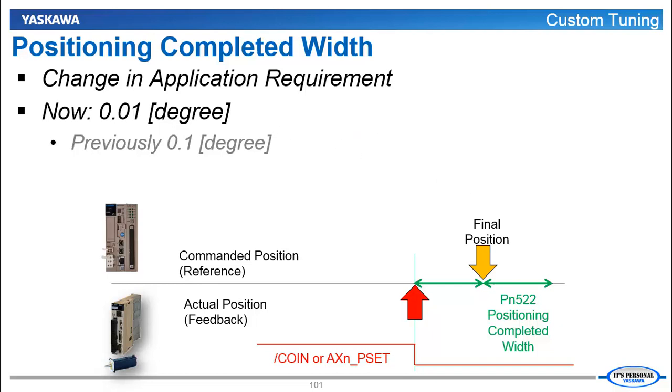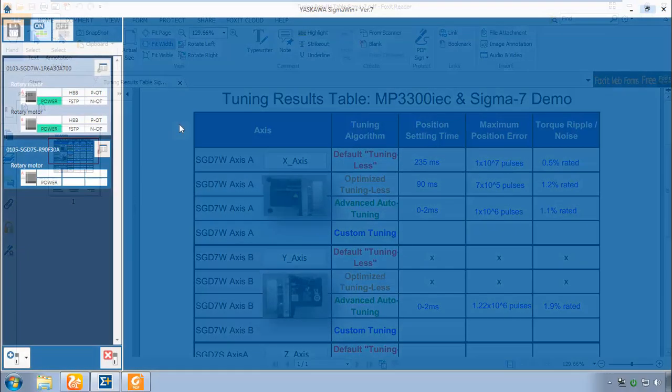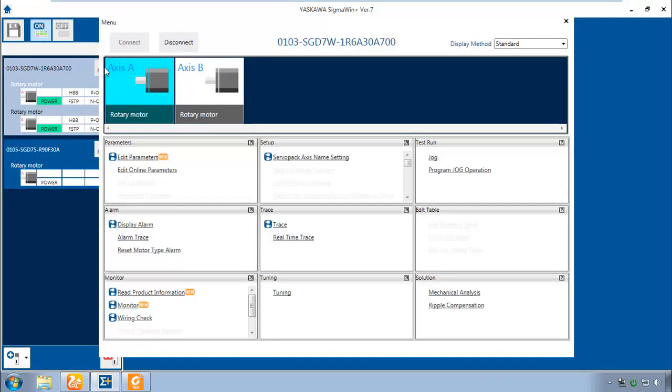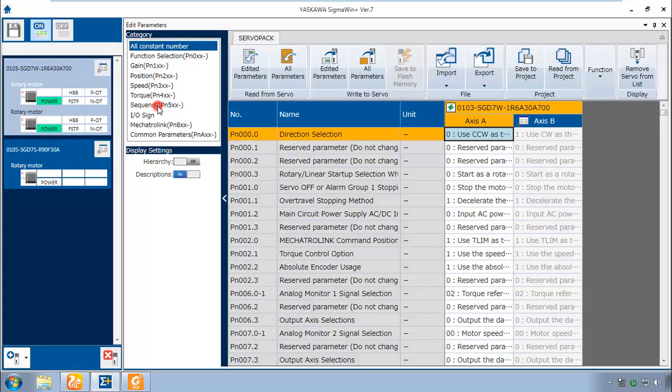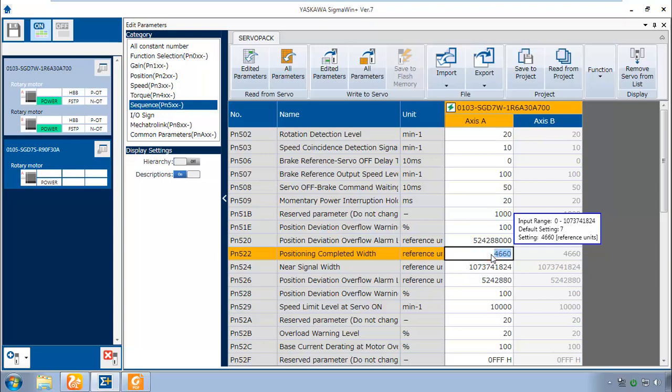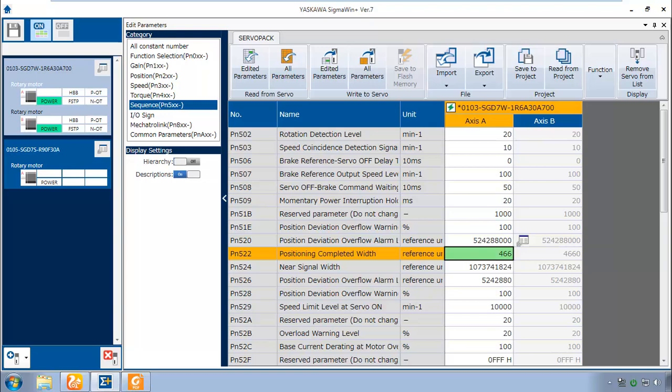So now to measure the coin signal, what parameter has to change? It's PN522, Positioning Completed Width. And what do we change it to? What value will give us 0.01 degree? Let's open up the parameters, go to the PN500s. And you remember we've set PN522 to 4660 which we had calculated equals 0.1 degree. So let's reduce this now to 466, and that will be 0.01 degree. Write that in there. And let's see now what the settling time is with this parameter change.